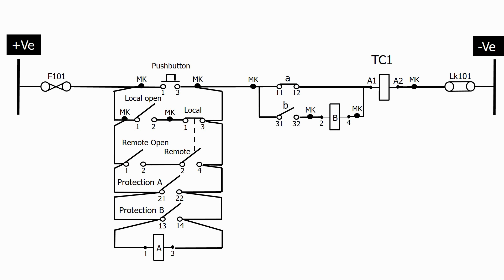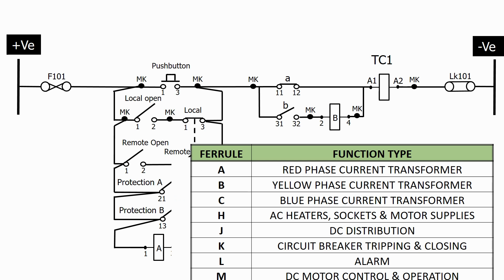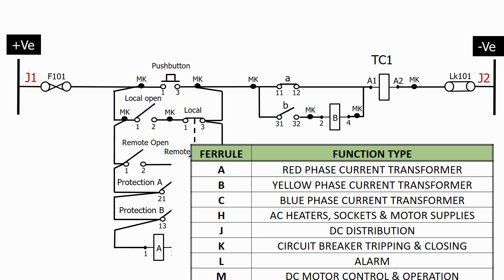Let's now add some ferrules. What ferrules should we use for the positive and negative busbars? It's common for these busbars to feed multiple types of circuits. So in this case we use the DC distribution ferrule prefix, which is J. Following a similar philosophy from the last circuit, we label the positive busbar J1 and the negative busbar J2.